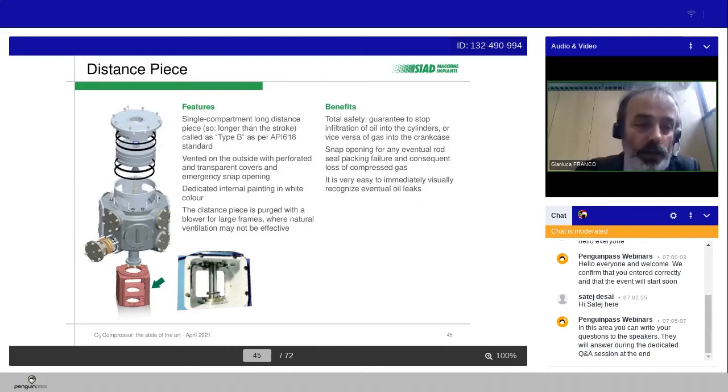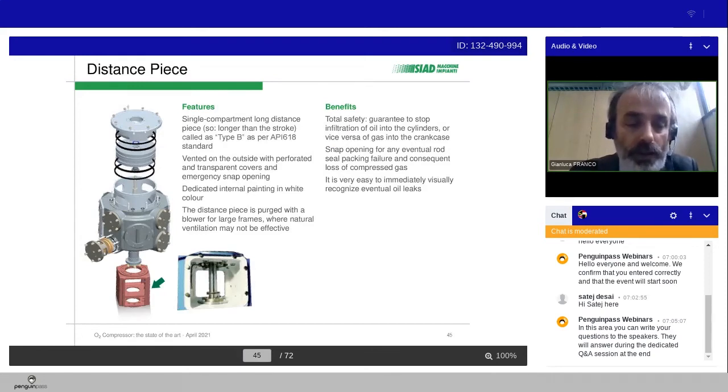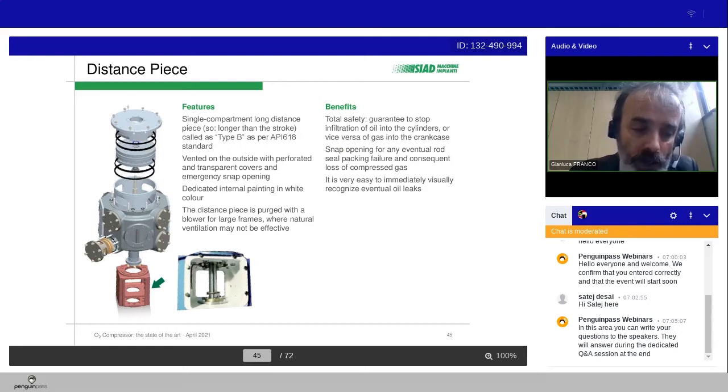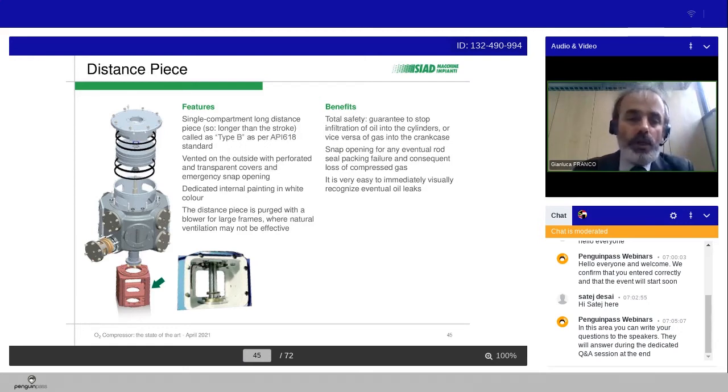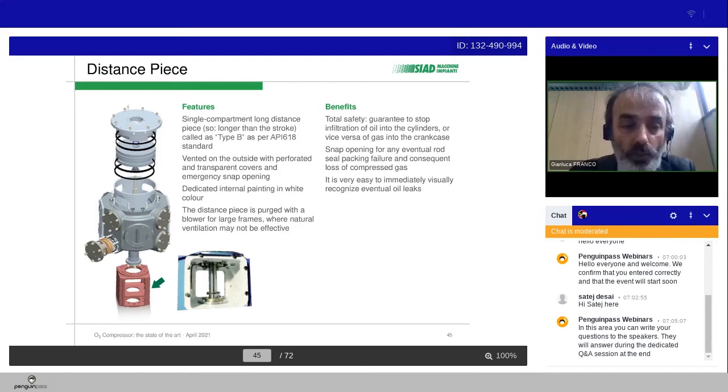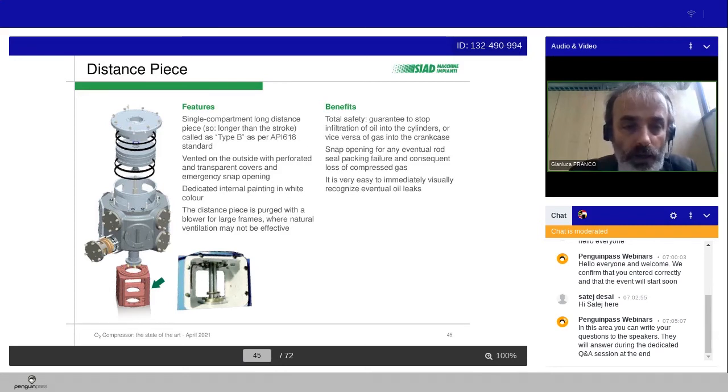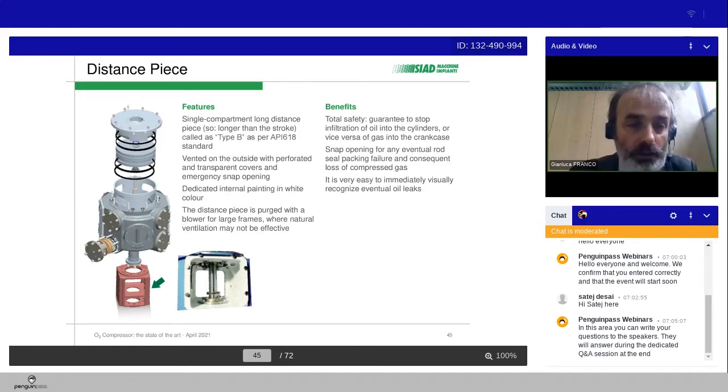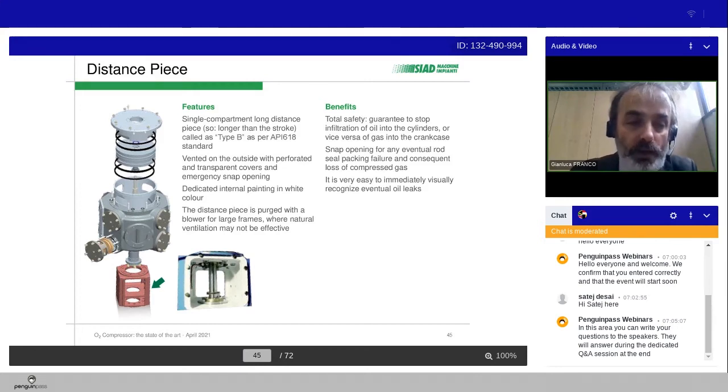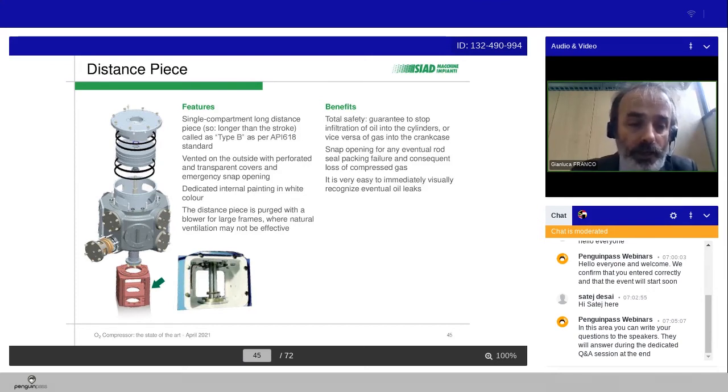We have now the distance piece. A distance piece is the element that separates the crank mechanism, so the mechanical parts of the machine, from the pneumatic zone, the cylinder, the valves and the piston group, where we have the compression of the gas. Typically, according to API 618, we can have a single compartment, long distance piece, longer than the stroke, and it is called the B-type, according to API 618 standard. It is vented on the outside with perforated and transparent covers, and emergency snap opening, and dedicated internal painting in white color.